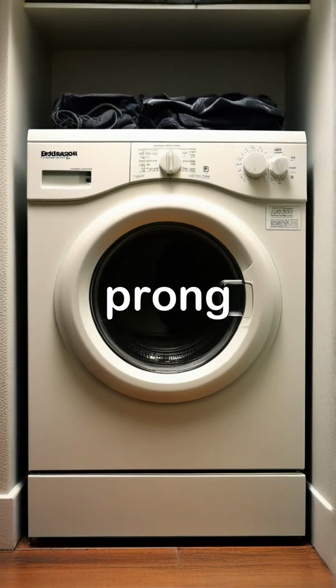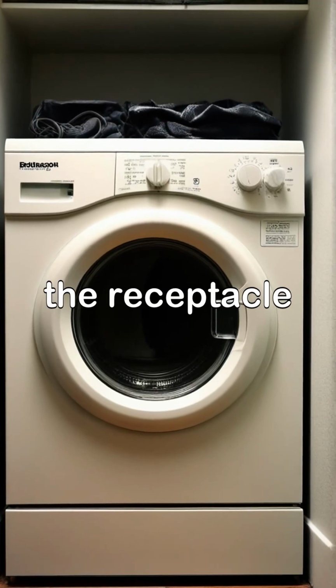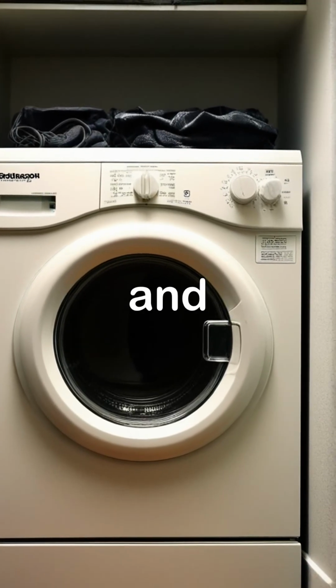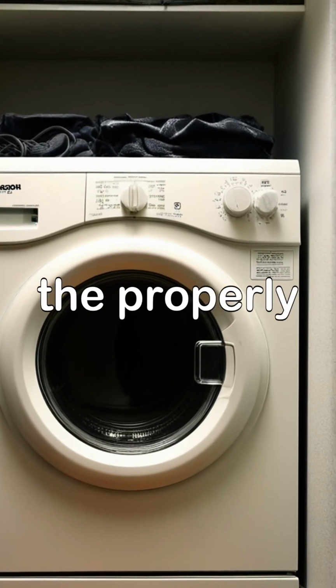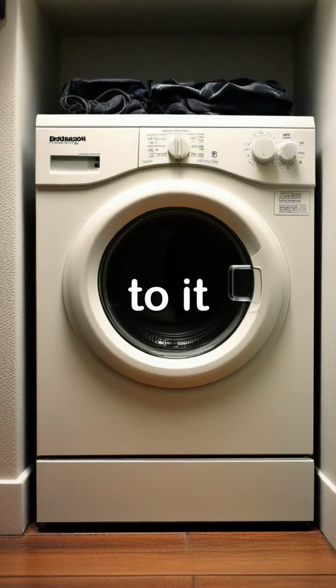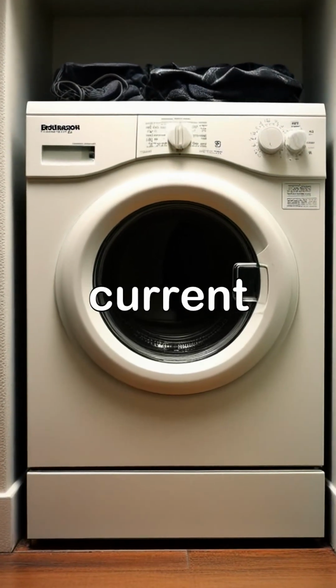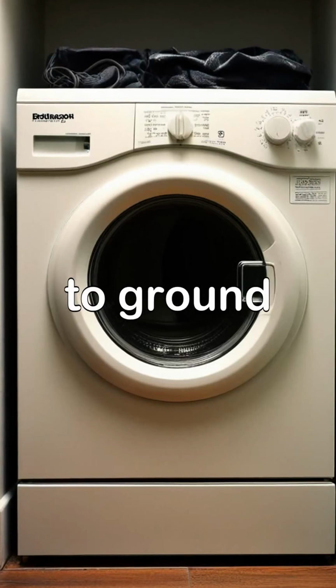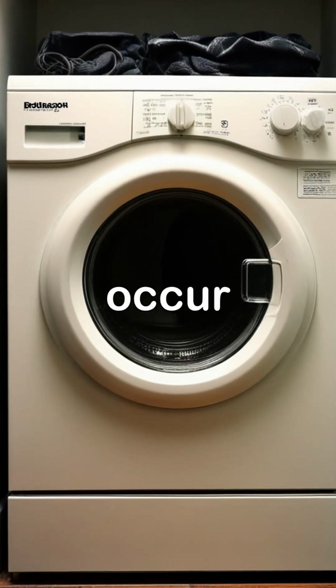However, if the grounding prong in the plug is missing or the receptacle isn't properly grounded and you happen to touch the machine and the properly grounded clothes dryer next to it at the same time, the fault current will flow from the washer through you to ground and a fatality could occur.